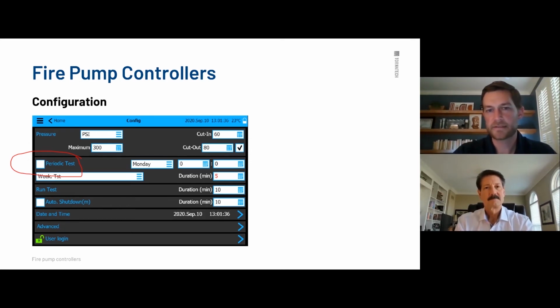And it'll run the test for whatever. If it's a diesel, it's 30 minutes. For the electric, it's 10. But you can also set it up to do a periodic test and do it automatically. So you can come in here and enable periodic test. You just click in that gray or that white box there, and you can have it come up, you know, as a weekly test, a bi-weekly, a monthly.